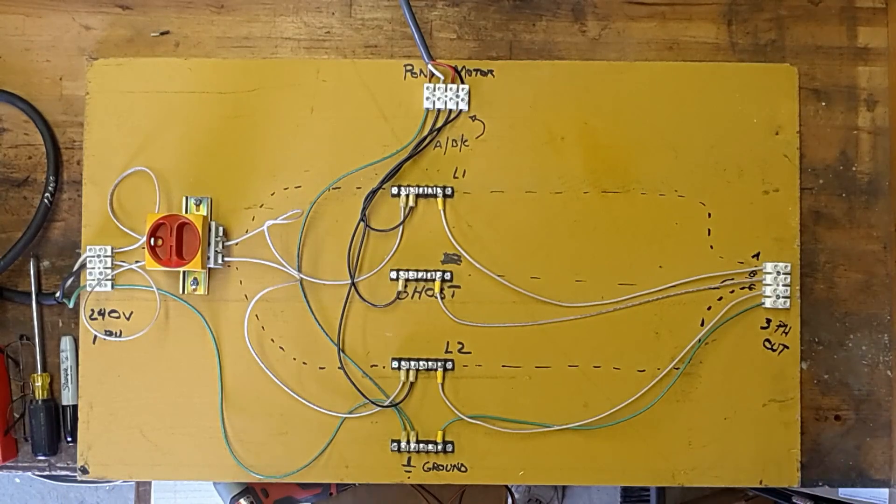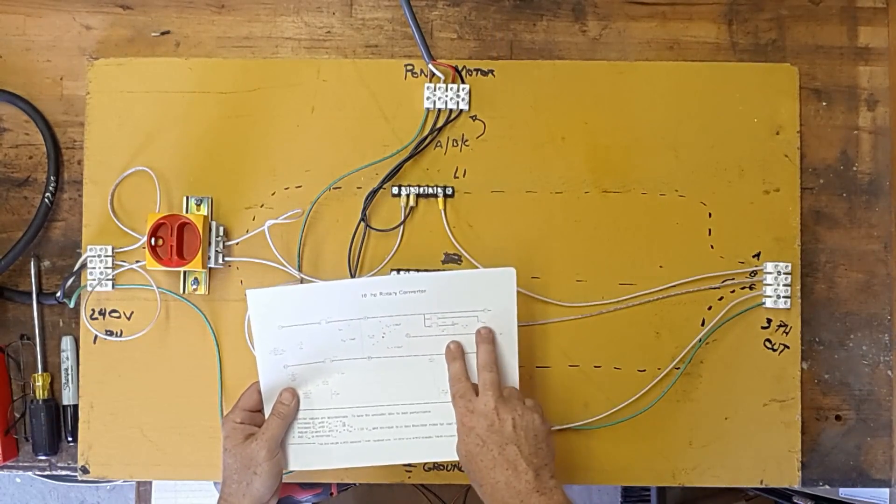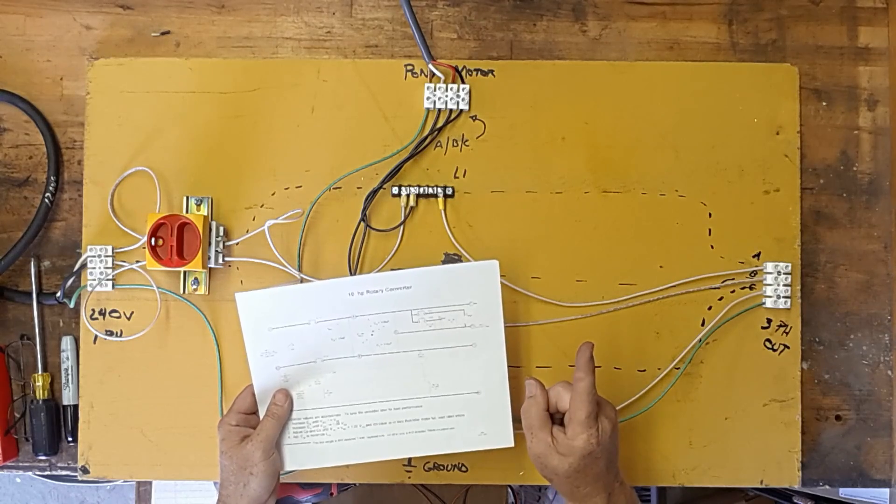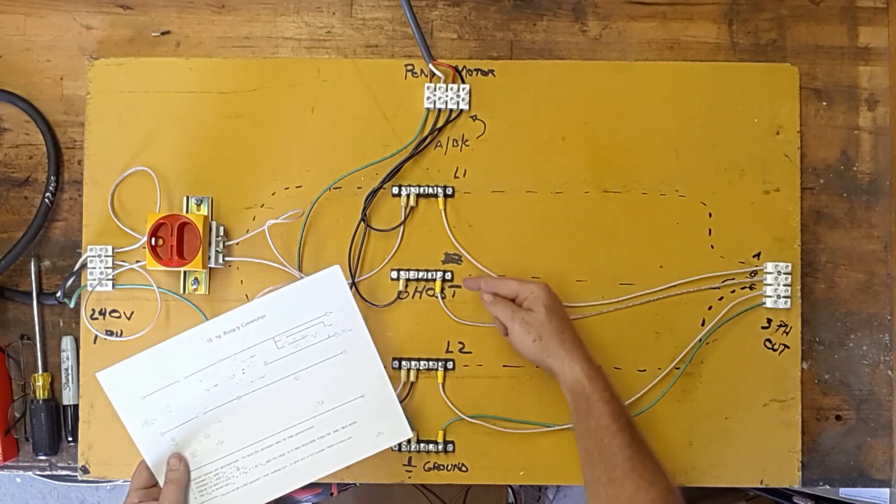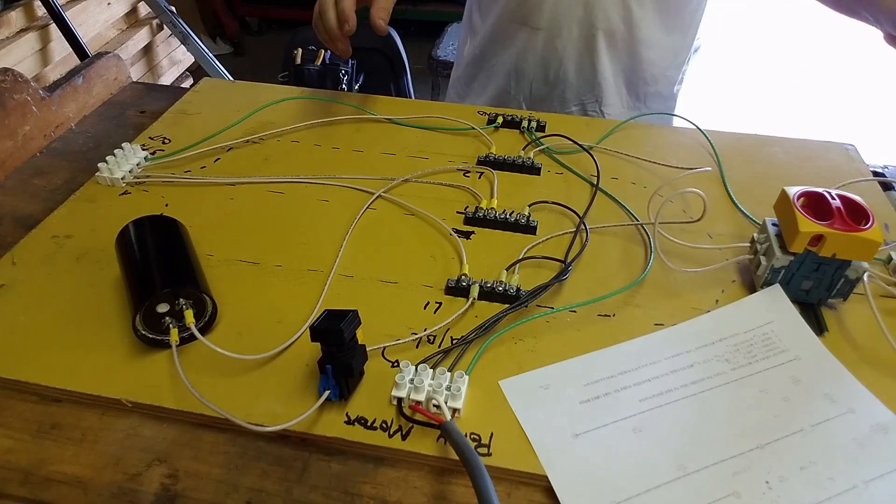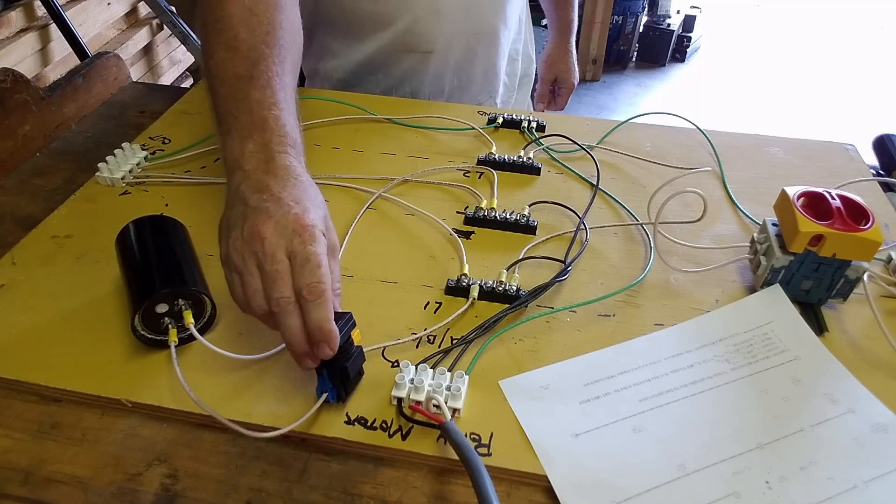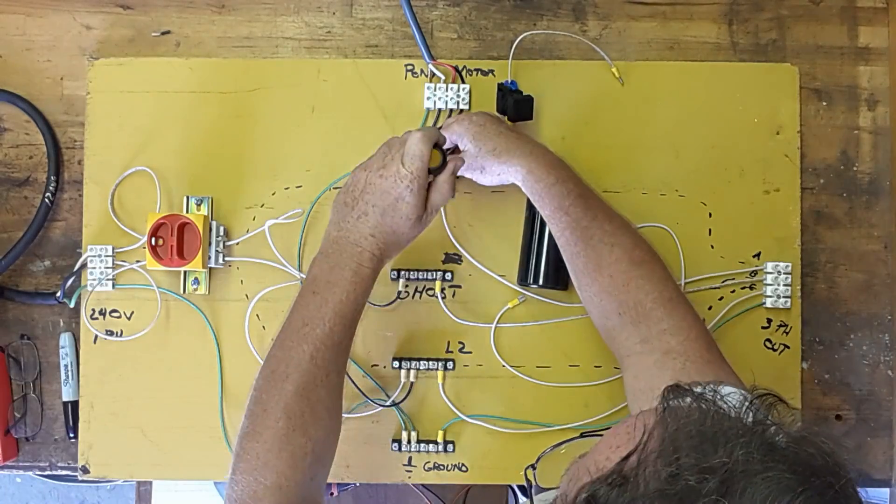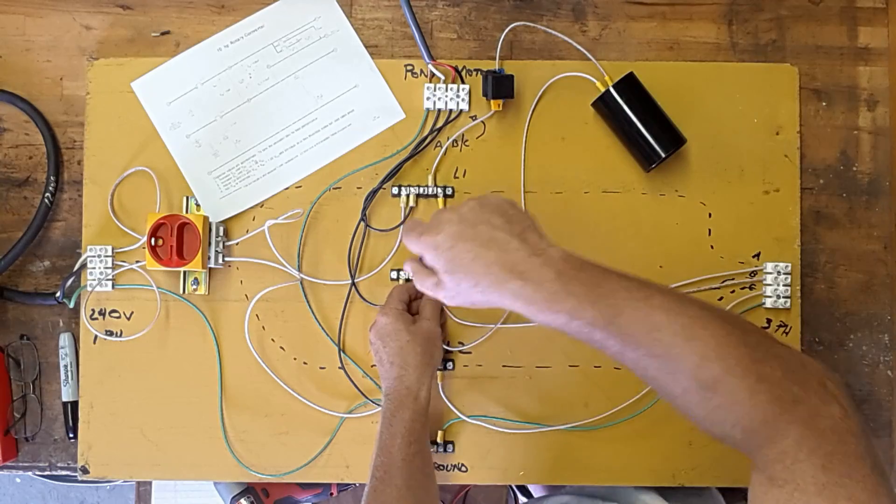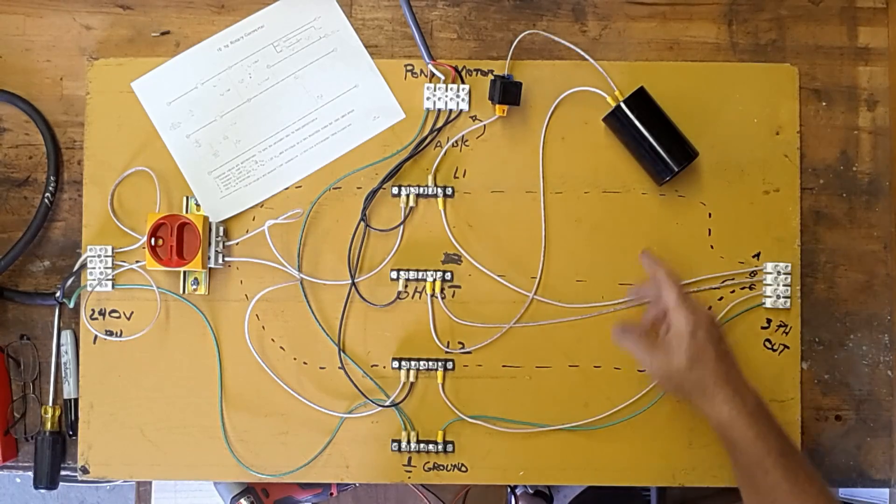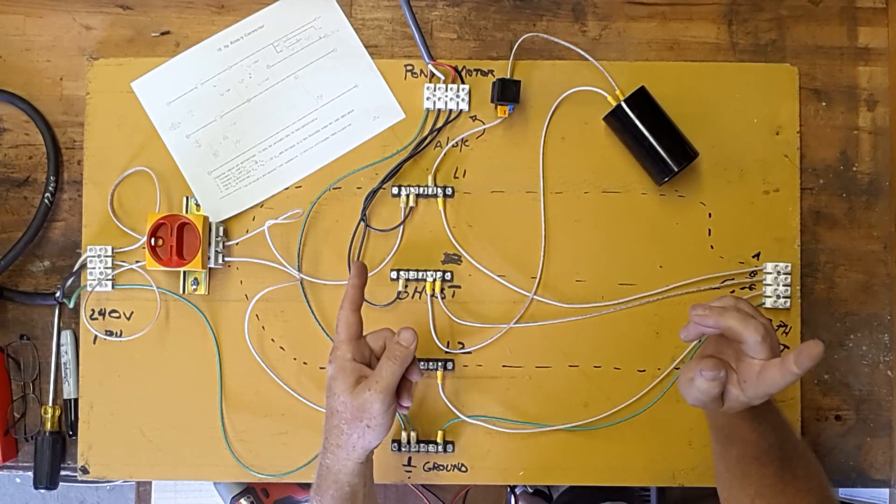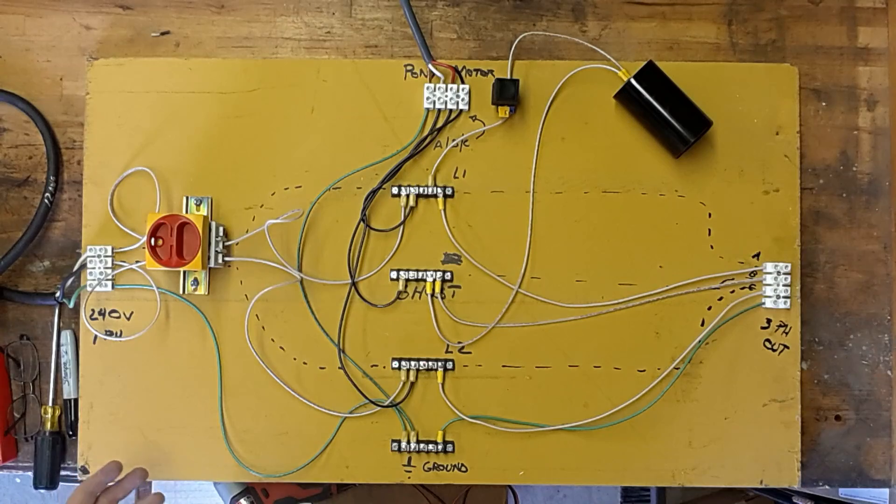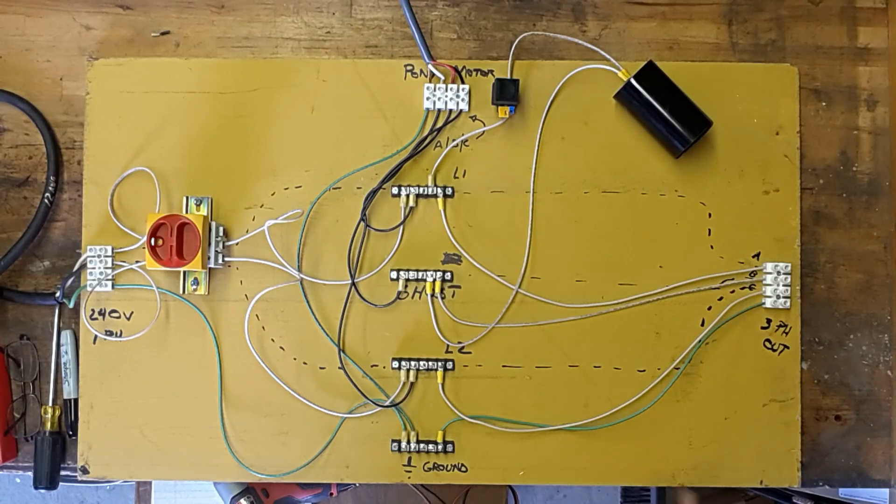However, this is not going to be an auto starting converter. In this drawing, it shows two start capacitors. We're not going to do that. We're going to use just one. Either way you slice it, the start capacitor goes between this leg and this leg. Here's our start capacitor. And here's a push button switch that we're going to use to activate it. So what this is doing for us is throwing the electrical fields out of balance so the motor starts to turn. And this is a momentary switch. We hold it, the motor starts spinning, we let go. Now at this point, we can start this whole deal. They will run with no capacitors in here. So let's give it a try. Let's just see what it does and do some testing.